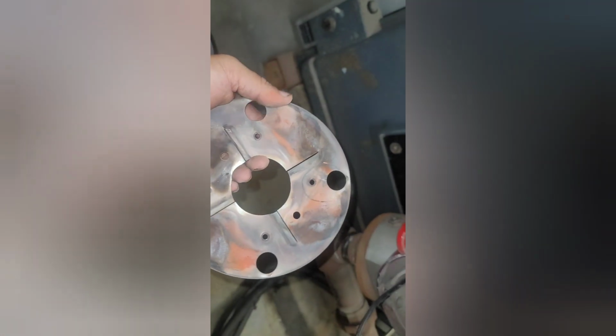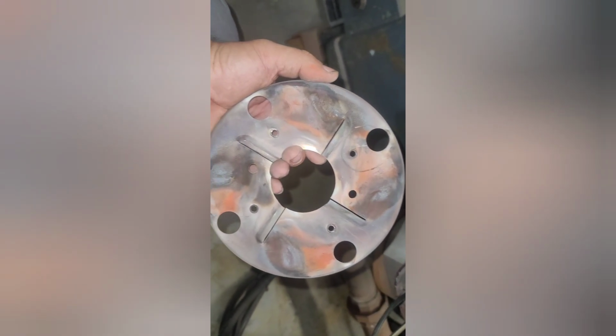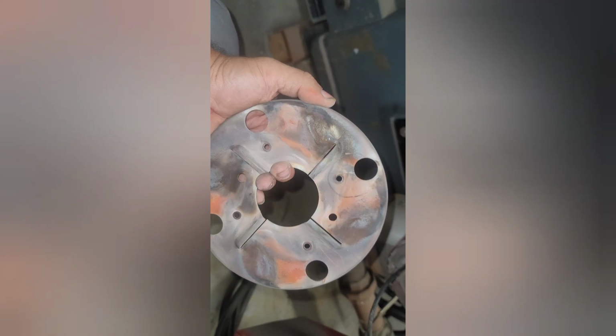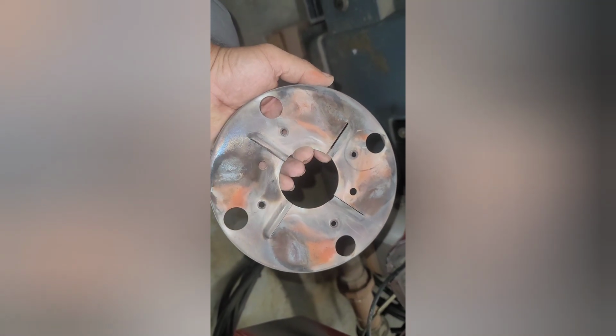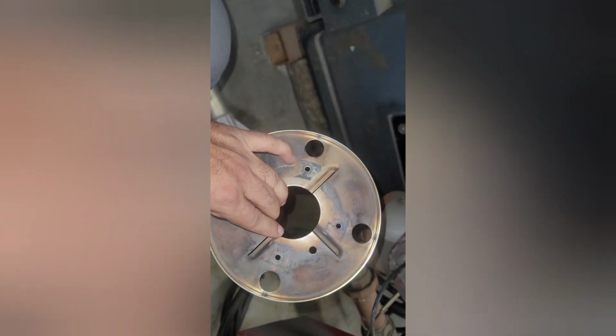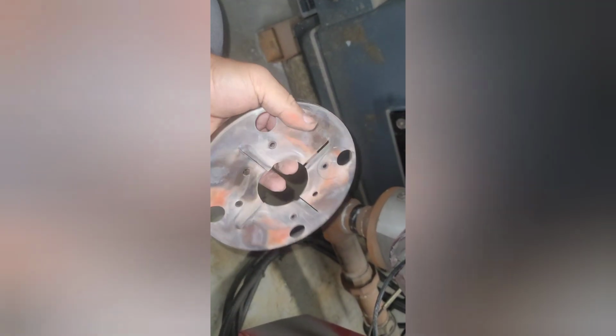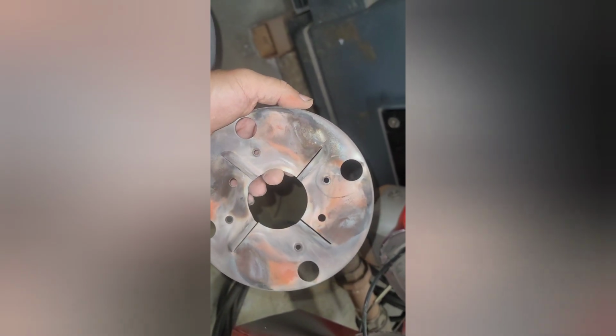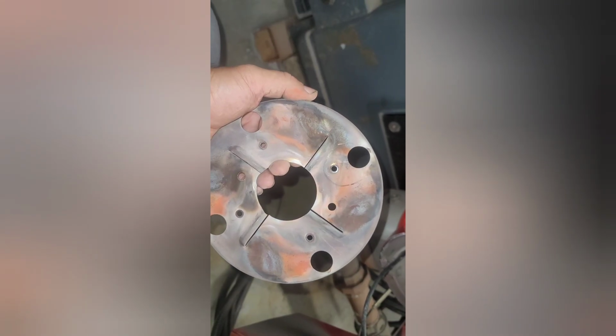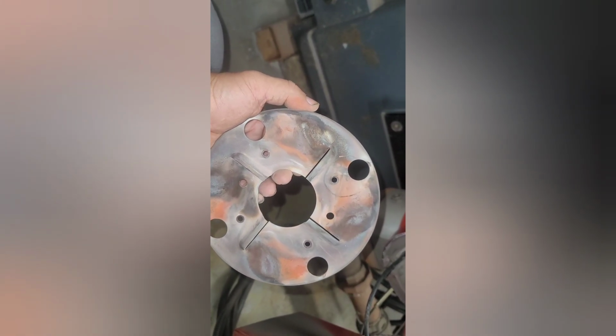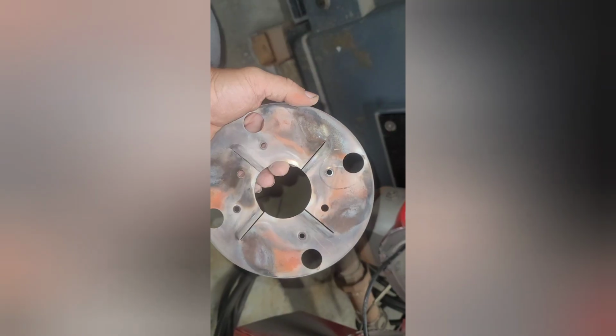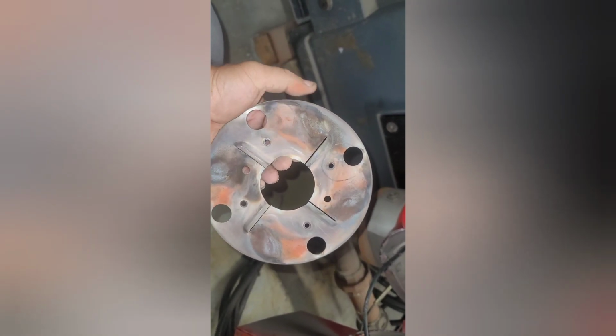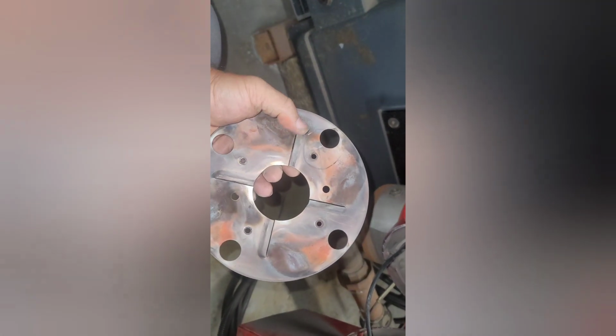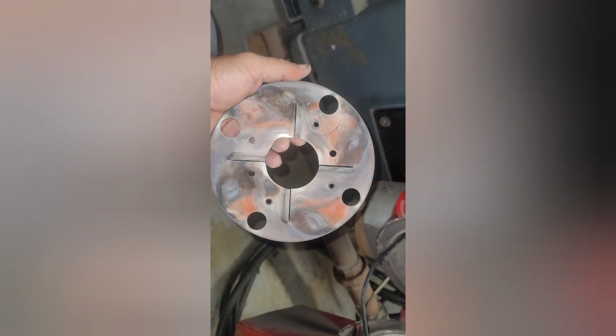Okay, so what happens, this is the metal, and now they are minor, but when they get super hot, the crack expands, which is not good, it reduces the boiler efficiency, or it's not even. So that's what the burner manufacturer recommends during the maintenance, just to observe the crack if there is any. So replace the plate, it's not much expensive, and once in a year we have to replace the flame rod and igniter. That's a part of the maintenance.